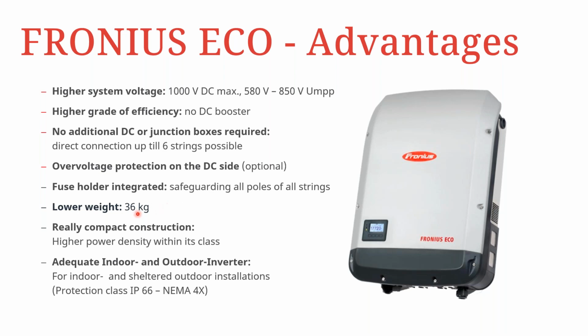So the inverter itself is quite light, and therefore, if you look at the power to weight ratio, the Fronius Eco inverter is actually at the top of its power class. In terms of protection, we said it's IP66 and NEMA 4X. So this means that these inverters can also be used either indoor or outdoor. It doesn't matter. The only thing to note is that this does not mean that the inverter can be operated in flooded areas. It means that it can withstand jets of water or rainwater, but never be submerged in water, of course.